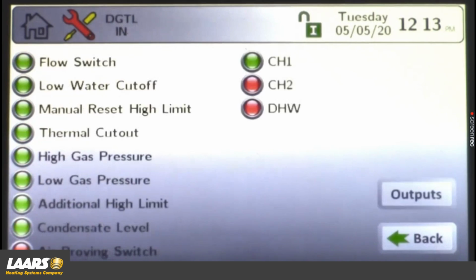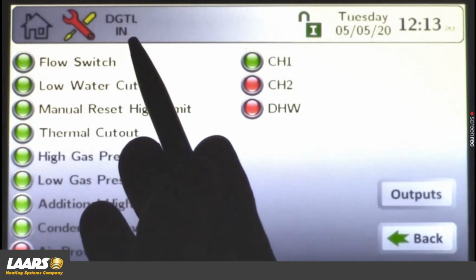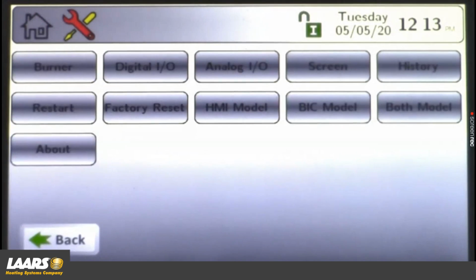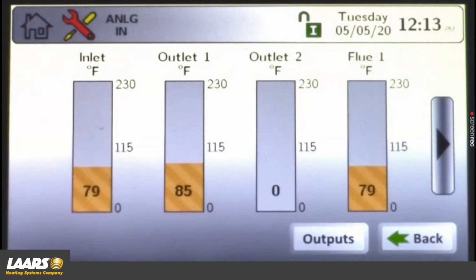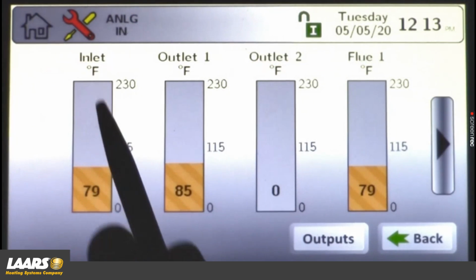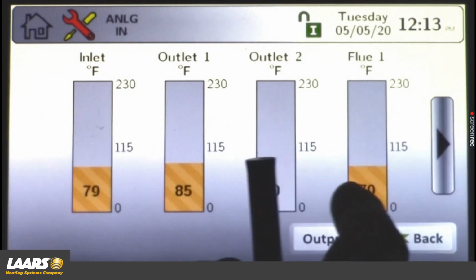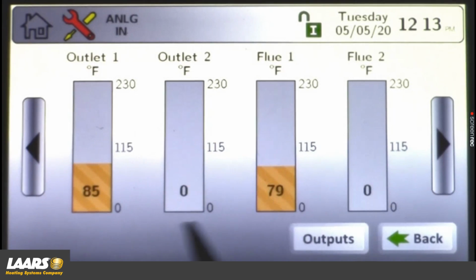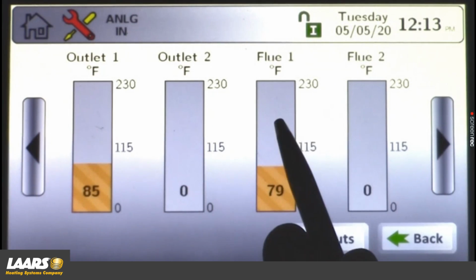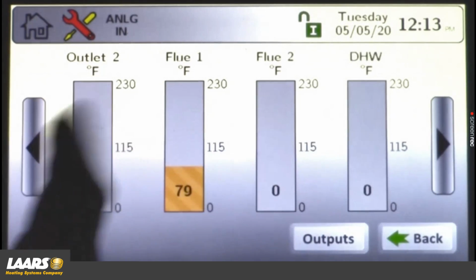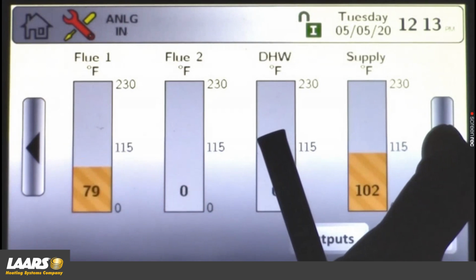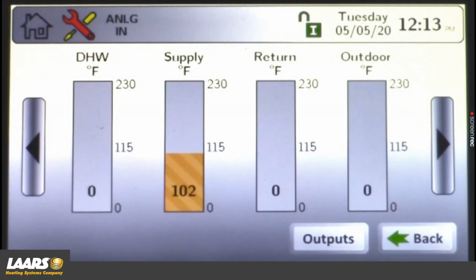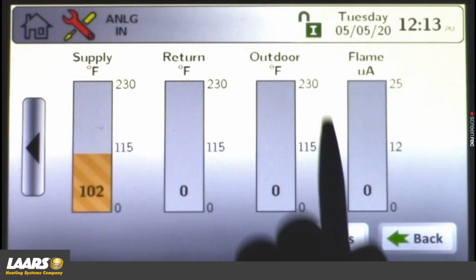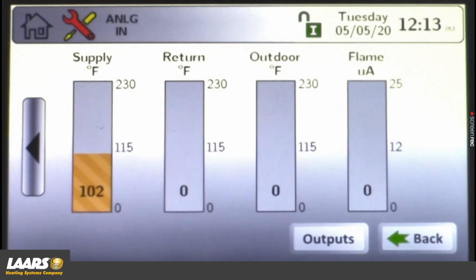I will now click the back button, or again on the navigation bar, I can come right back here to service. Analog I&O will give us even more information, showing an inlet temperature and outlet temperature. If we have a stack sensor in a boiler, it'll show us the flue temperature. Depending on the product, you might only have one stack sensor, or a product like a Pennant would not have a flue sensor. So you can just scroll through. We can see our supply temperatures, return temperatures, and outdoor temperatures if we were hooked up with an outdoor sensor. And if the boiler was actually running, we would see a flame signal appear.